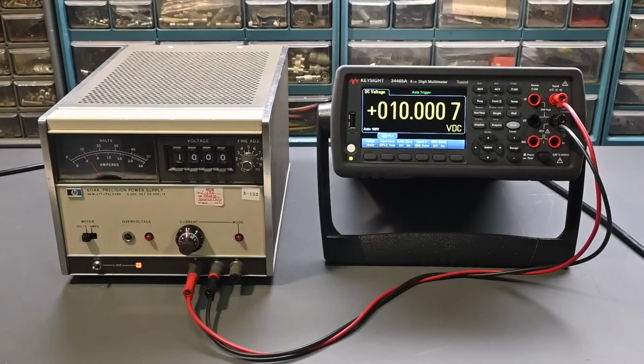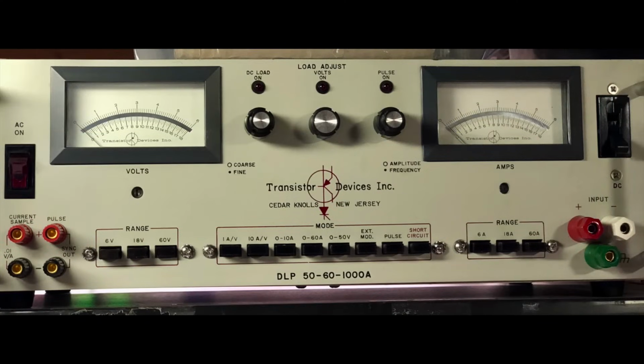But all of those Dynaloads, which are electronic loads, have a modulation input. So for example, on the DLP 5060-1000A, that's an analog input, it has knobs on the front panel. But if you use the modulation input, which can come from this power supply, it doesn't have to be changing, it can be a fixed DC signal. By controlling it with this HP 6114A, now that Dynaload has a very accurate and stable load that it applies, or a current that it would draw from whatever you're testing. It could be a battery or a power supply, something like that.